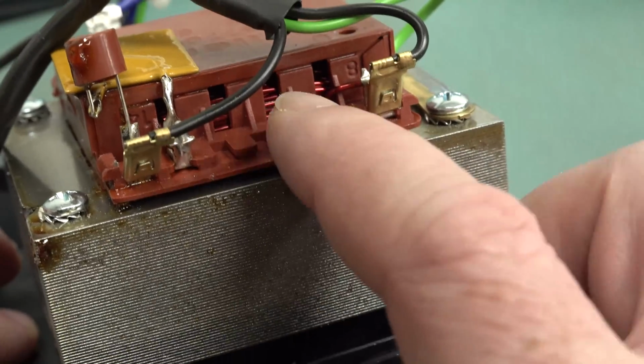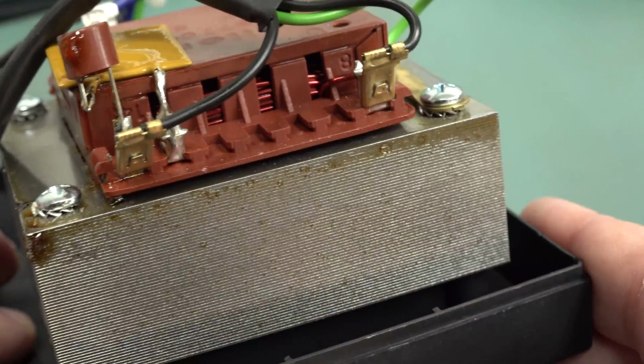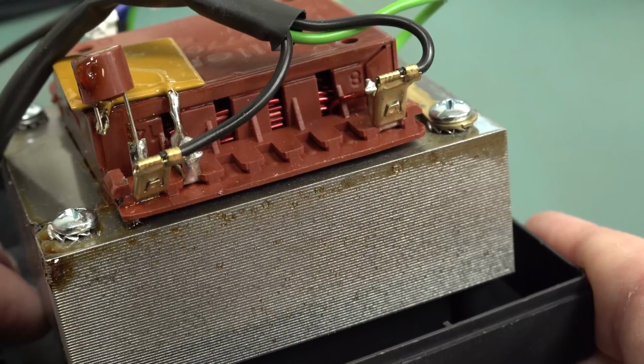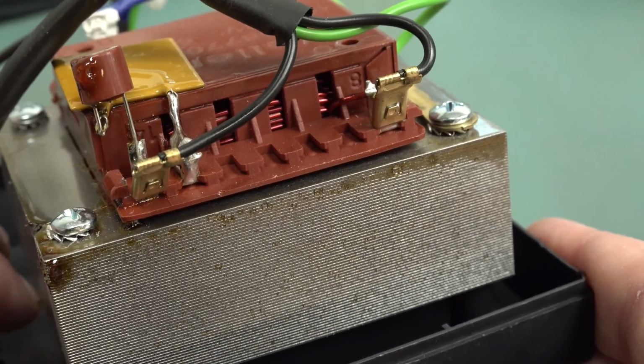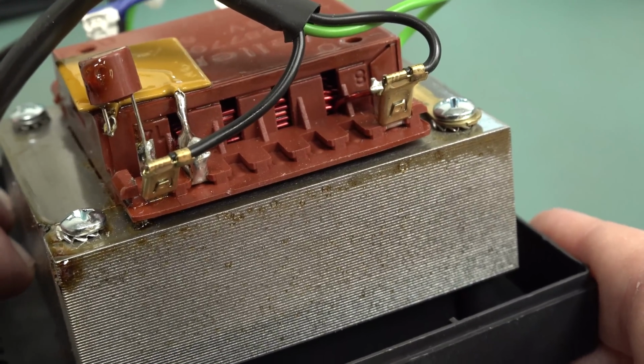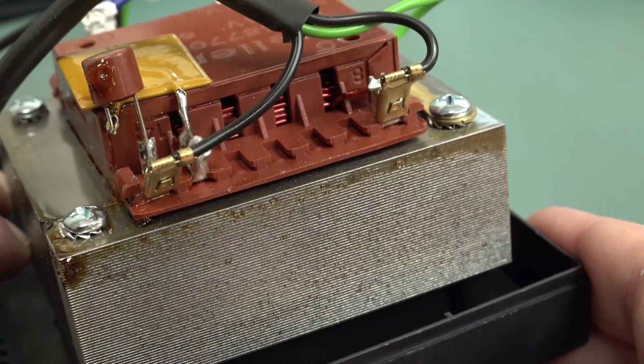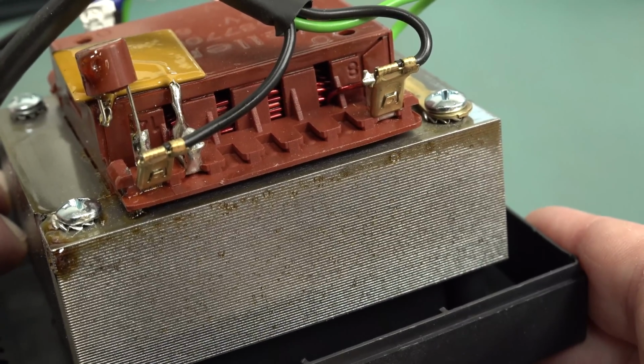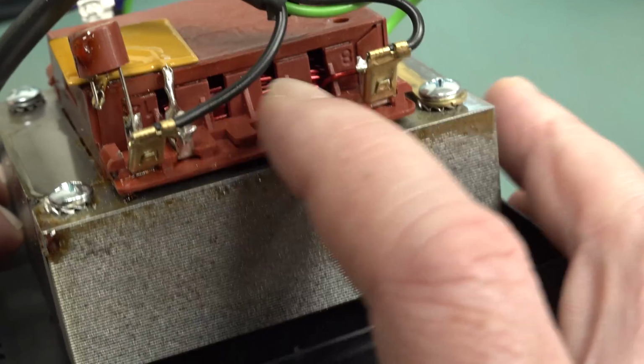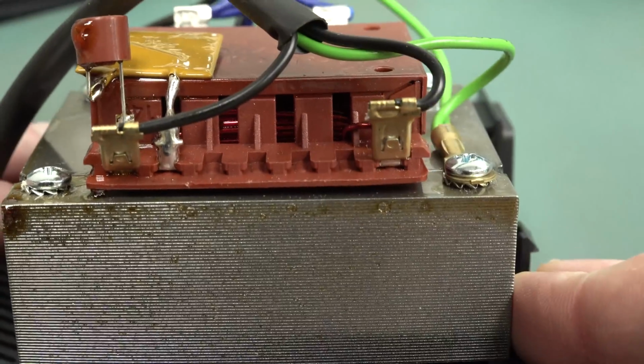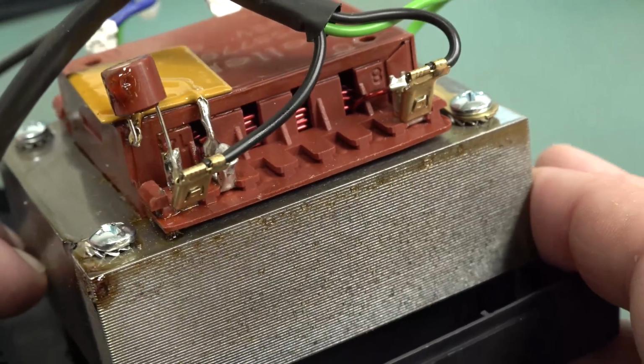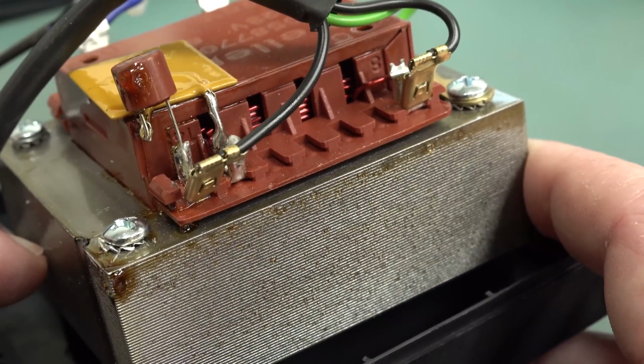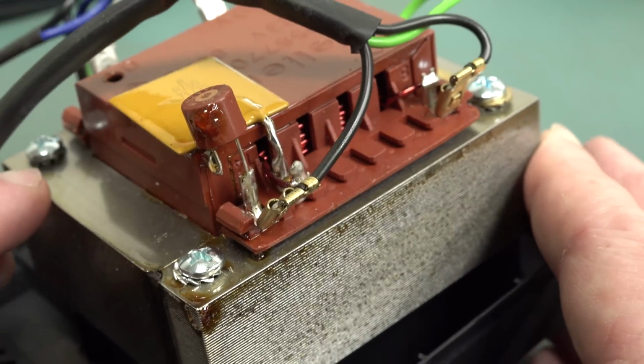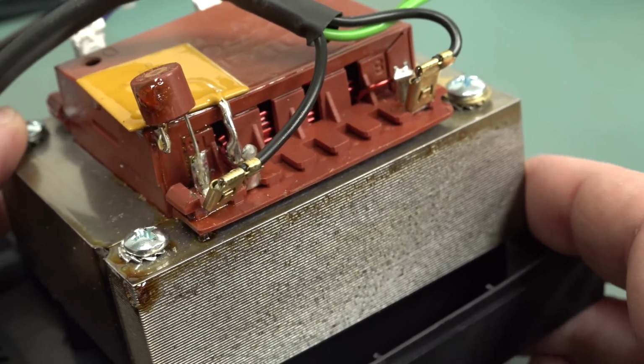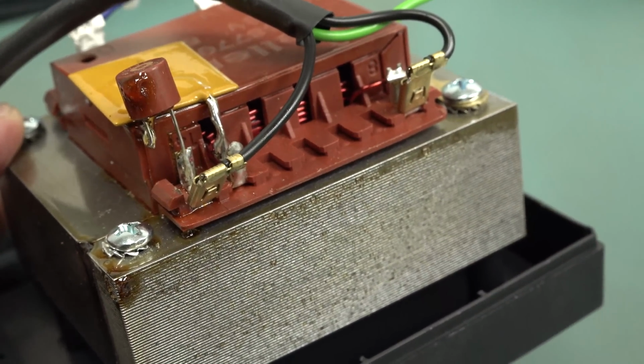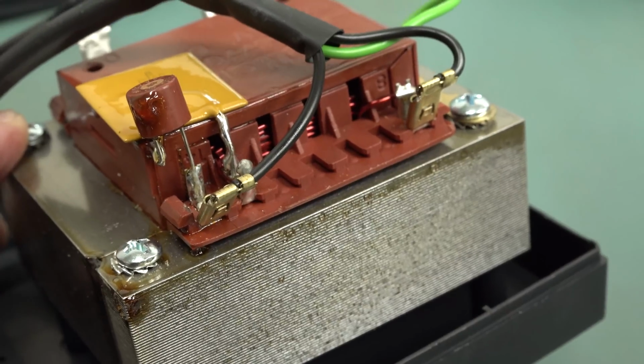So I can only presume it burnt the enamel off the wires. Once that amount of smoke escapes from something like a transformer, even if I powered this up again and it worked, I wouldn't trust it, because that smoke must have come from the enamelled wires on there. So that just breaks down the insulation. Yeah, not a good thing. So I would not trust that and reuse it, even if it worked after a smoking overload like this.